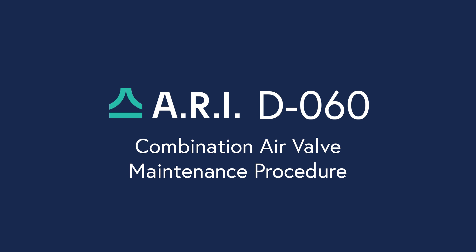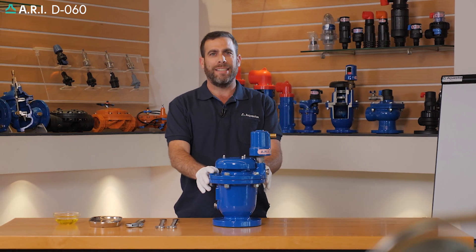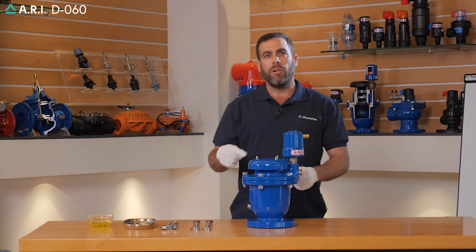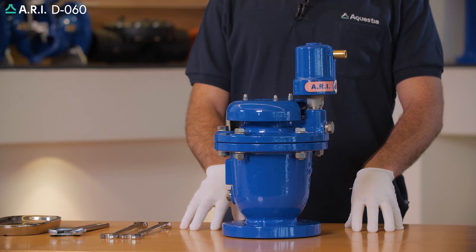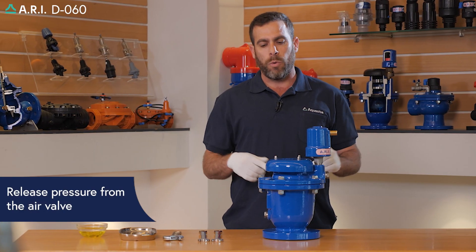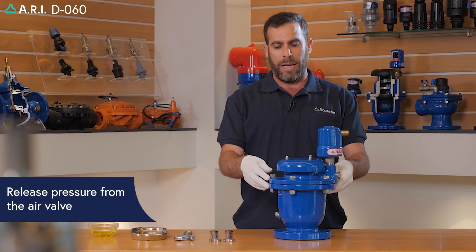We are going to conduct maintenance on an A.R.I. D-060 air valve. First, we'll start by closing the isolation valve under the air valve. After we close the isolation valve, we're going to release pressure from the air valve itself.